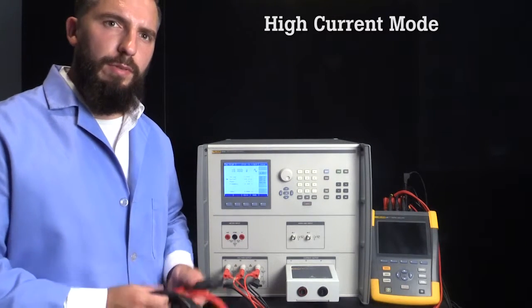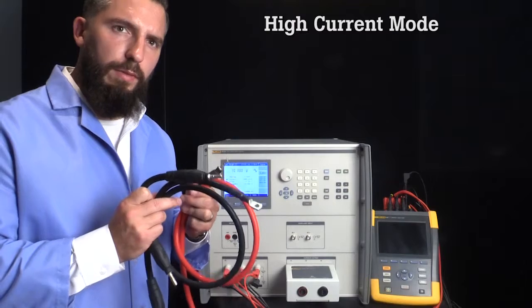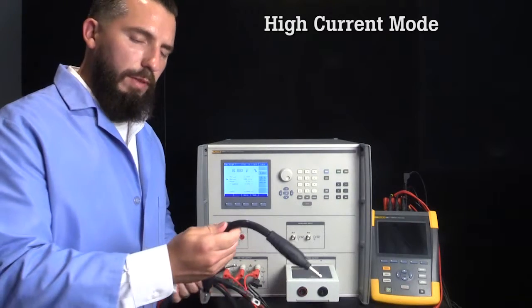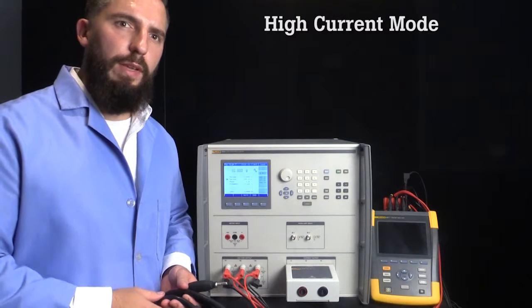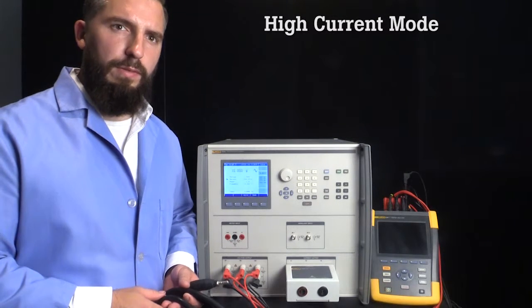The 90 amp high current adapter comes with two high current cables for connecting to the unit under test and a shorting plug. The 90 amp output can be used to drive the 52120A current coils, 25 turns and 50 turns, to simulate a maximum of 4500 amps, useful for calibrating current clamps.